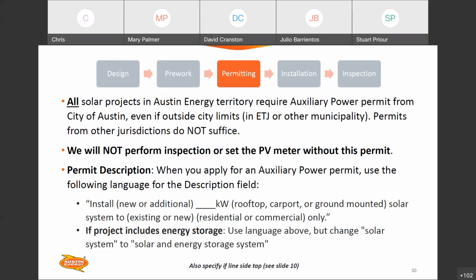You're not required to follow this, but we recommend including this type of language in your permit description to better specify your project to the permitting department. If your project includes energy storage, include language about the energy storage system in the permit description as well, and remember to reference the line side tap if you are using one — that should go into the permit description too. We prefer not to see permit descriptions that just say 'installation of solar panels'; we prefer more specificity about the exact type of project based on these parameters.